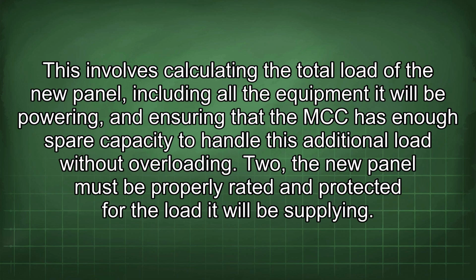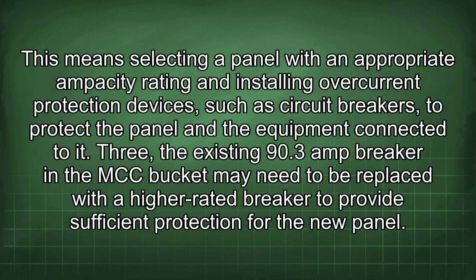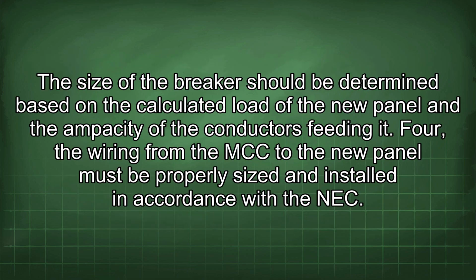2. The new panel must be properly rated and protected for the load it will be supplying. This means selecting a panel with an appropriate ampacity rating and installing overcurrent protection devices, such as circuit breakers, to protect the panel and the equipment connected to it. 3. The existing 90.3 amp breaker in the MCC bucket may need to be replaced with a higher rated breaker to provide sufficient protection for the new panel. The size of the breaker should be determined based on the calculated load of the new panel and the ampacity of the conductors feeding it.